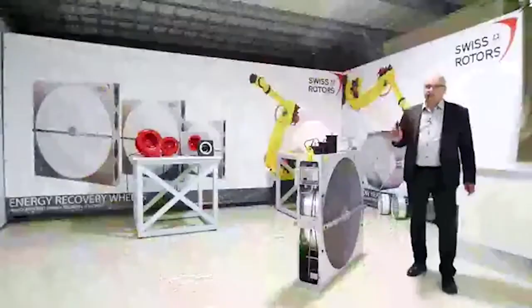So this is, as I mentioned, a very simple connection diagram. As you see in this presentation, we just have a few buttons and few terminals. This is the test button just to start. If you push here, we start the wheel, and it starts to rotate and shows some own self-test. Then we have a dip switch. With this dip switch, you can change the speed. If you don't have a variable speed, you can have a different, constant speed. But we usually set up the parameters in the controller so that the condensation wheels rotate at 10 RPM, like we can see here.